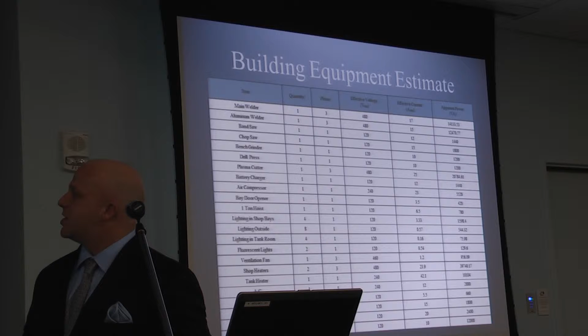And here is a list I made of all the equipment I anticipated would be in the workshop. You can see over here all the items, their quantity, how many there will be, the phase, the voltages, the currents, and the volt-amp apparent power. And here is the worksheet I used to calculate the size of the transformer with all the same values, except the load I put in kVA, which is how the transformer is rated. The total kVA calculated for the transformer was 44.78 kVA. So the size of the transformer that would supply this apparent power rating was 50 kVA.